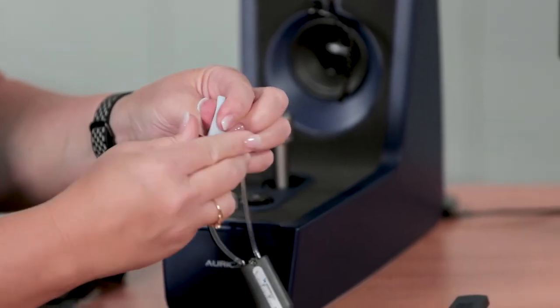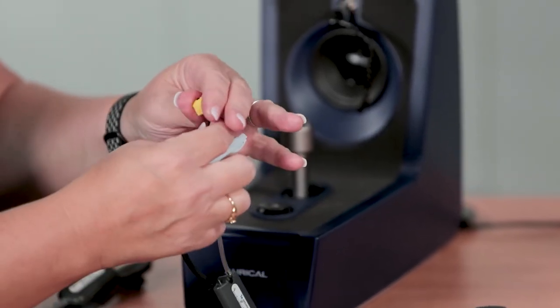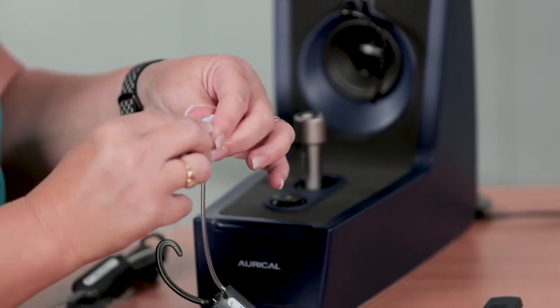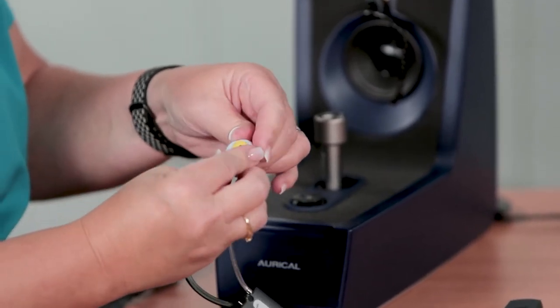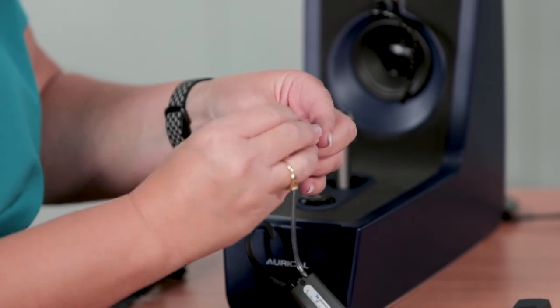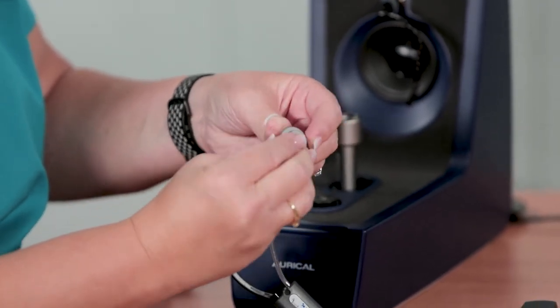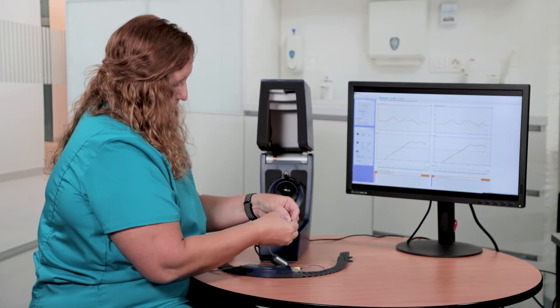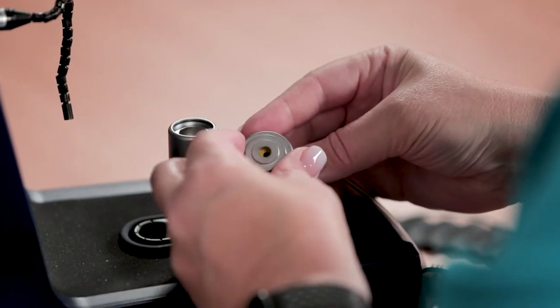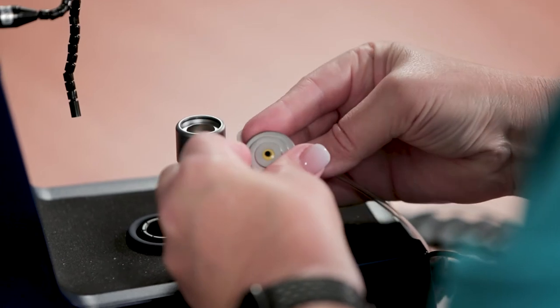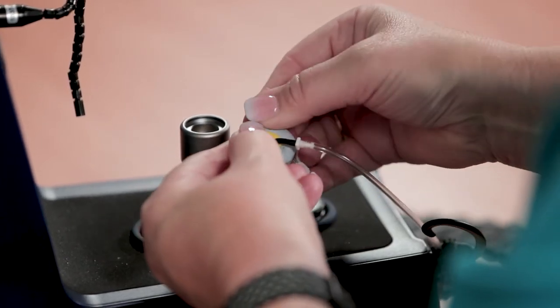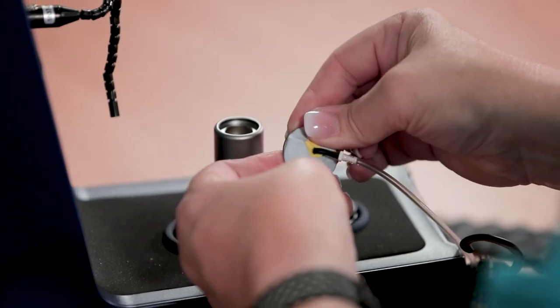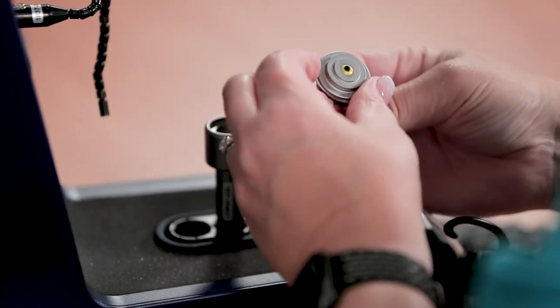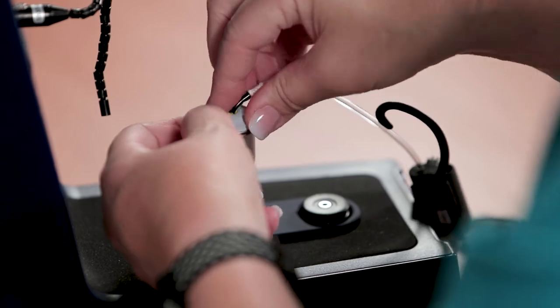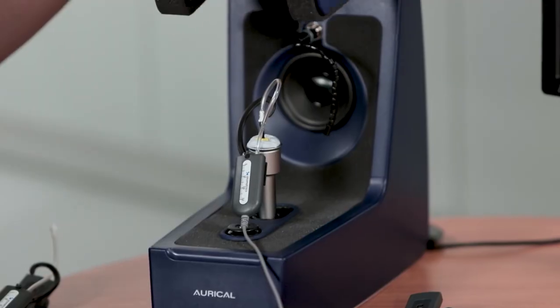Begin by rolling out the acoustic putty into a tube shape and wrap it around the foam insert tip. Create a tight seal with the acoustic putty by pressing it onto the HA1 adapter. Carefully line up the acoustic opening of the foam tip to the hole in the middle of the HA1 adapter. Check that the opening in the middle of the adapter is still clear of putty and the acoustic opening of the foam tip is clear. Snap the HA1 adapter onto the 2cc coupler. Place the coupler microphone in the microphone port, furthest from the Aurical HIT speaker. Close the Aurical HIT lid to measure the coupler response.